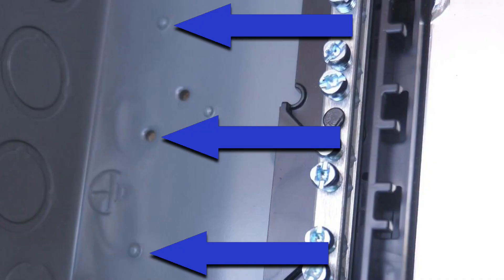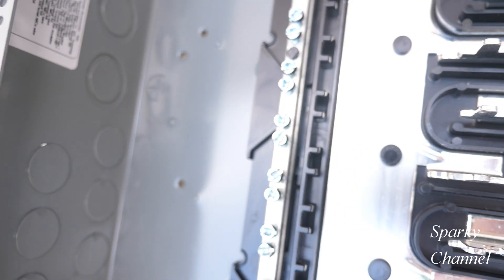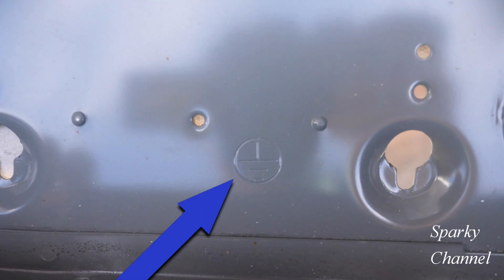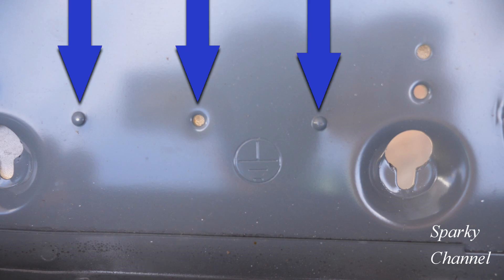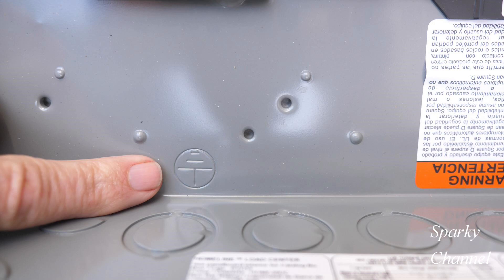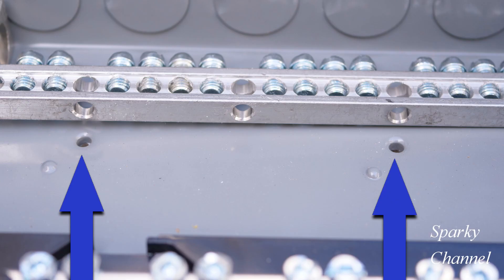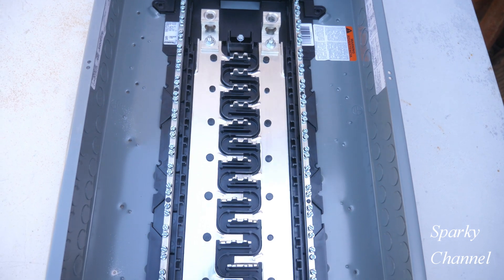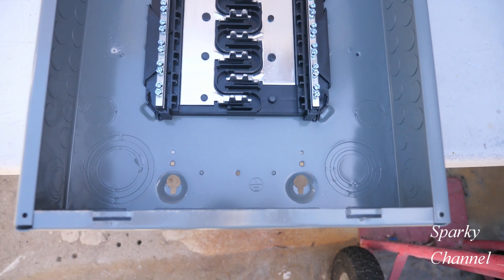On the left side of this Homeline load center you will see a ground symbol, a hole for a screw, and two nubs which can be used to install a ground bar. Moving down the panel to the bottom of the load center — farthest away from the main lugs — we find another ground symbol, two more nubs, and another hole for a screw. On the opposite side of the load center you'll find another grounding symbol, two more nubs, and another screw hole. Homeline also provides areas on both sides where you could use two screw holes and no nubs.